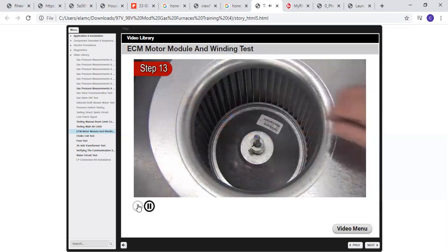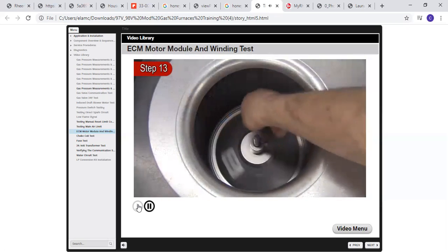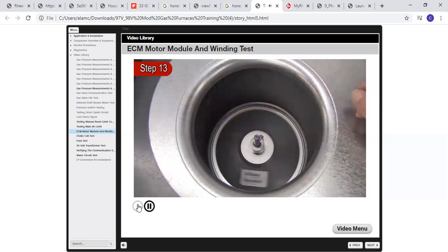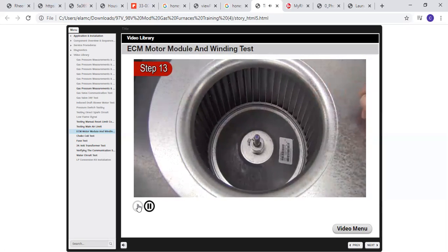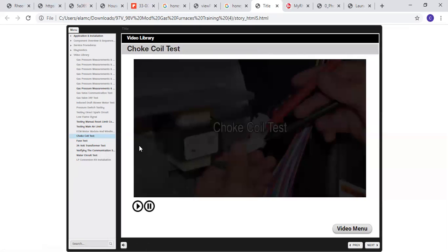Step 13. Spin the blower shaft of the motor. If the motor spins freely and the motor windings check out okay, replace the module. If the motor does not spin freely, replace the motor and the module. Okay, generally speaking, if it's under warranty, they're going to have you replace both the motor and the module, as it's a warranty issue. We'll go into the choke coil test.